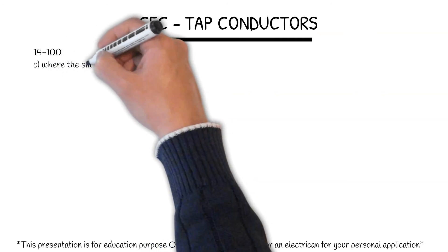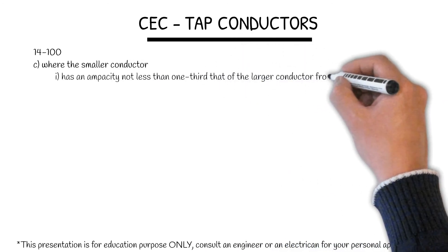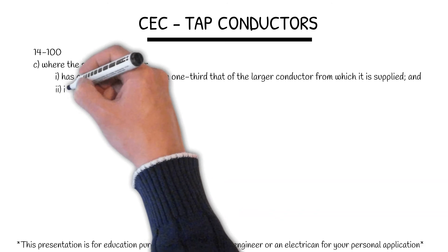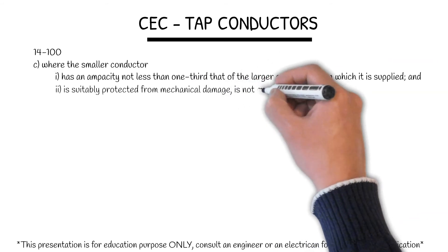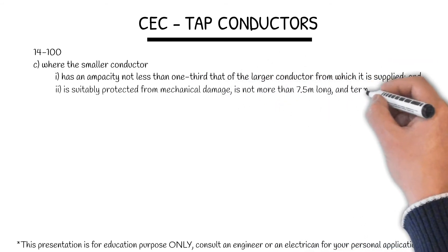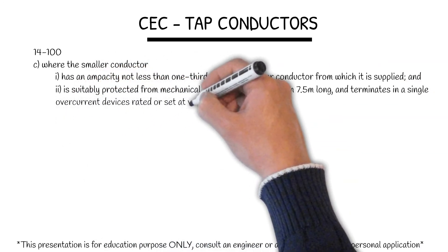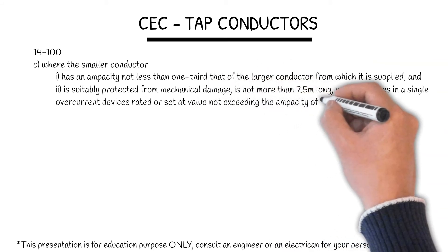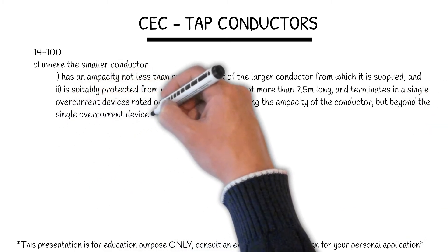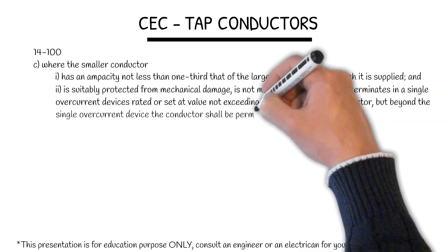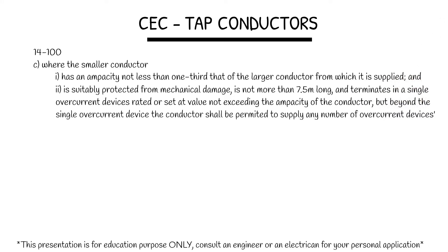14-100 Subrule C: the smaller conductor has an ampacity not less than one-third that of the larger conductor from which it is supplied, and it is suitably protected from mechanical damage. It is not more than 7.5 meters long, and terminates in a single overcurrent device rated or set at a value not exceeding the ampacity of the conductor. But beyond the single overcurrent device, the conductor shall be permitted to supply any number of overcurrent devices.